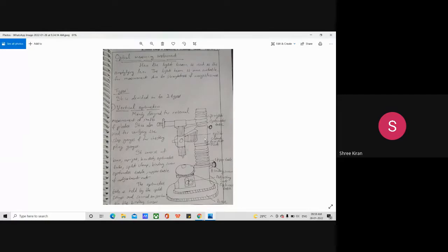What happens in this is the upright is mounted rigidly on this base, which is made very heavy and wide so that it imparts more stability. Then the upright consists of a ground shaft on which a large pitch thread of special form is cut, which provides an easy grip for the bracket.